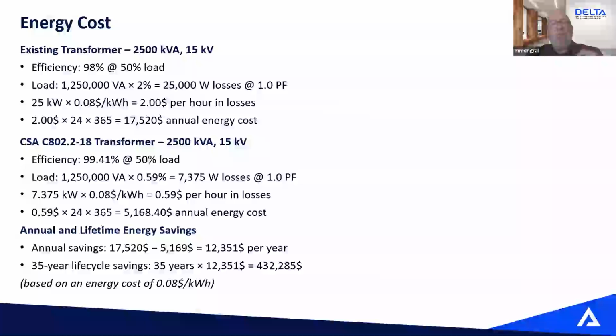How can I calculate or figure out the cost of my energy? There are different ways to calculate it. So let's say you have no information, no losses, no efficiency, nothing. At least you can go with the following. If you have an existing transformer, 2,500 kVA, 15 kV class, back in the day they were efficient at more or less 98%. So let's say we use that 50% load. So our load will be 1,250,000 VA, which is watts, times 2%, which is your losses. So that equals 25 kilowatts, 25,000 watts of losses at one power factor.